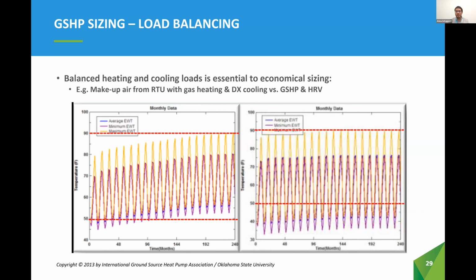These plots of entering and leaving water temperatures from the ground heat exchanger show that the initial case on the left would tend to warm the ground over time and lead to a decrease in system efficiency. On the right, we can see that the second scenario has a much more subtle change over time, yielding more consistent long-term performance.